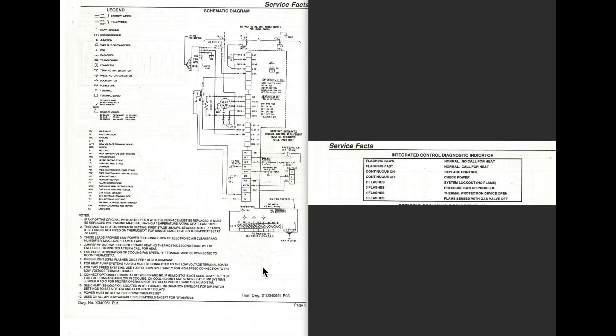This one, we're going to do the sequencing of this IFC controlled furnace. As I've said in the earlier video, this is way different of sequencing because you can't follow the wires. They all go to the board. The board makes the decisions on what to do.